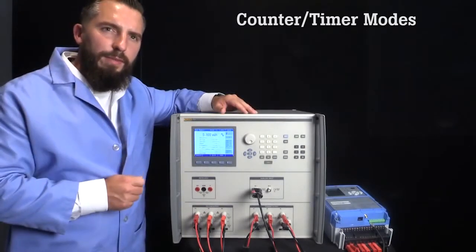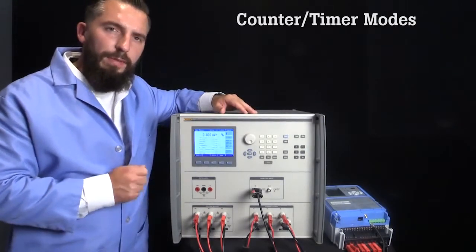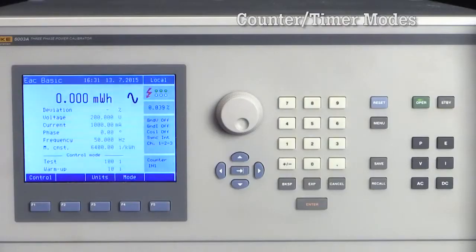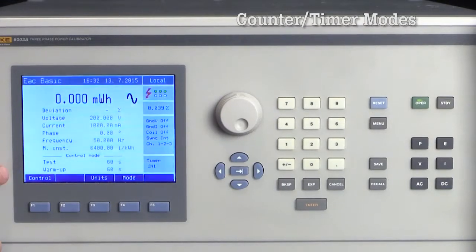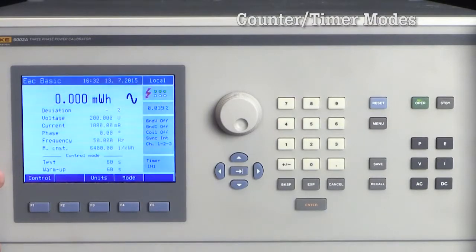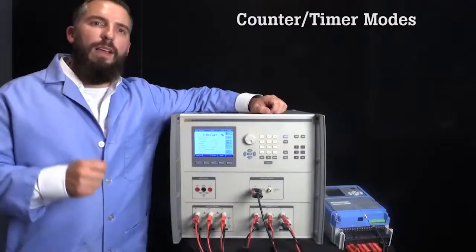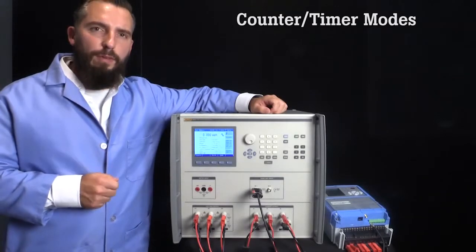To demonstrate, I've configured this test for 200 volts AC, 50 hertz, and 1 amp. If I use the counter mode, the 6003A lets you specify the warm-up pulses from the meter under test. If I were using the timer mode, I could set how many seconds I want the warm-up time in the test to run for, as I show here. For this demonstration, we will use the counter mode.